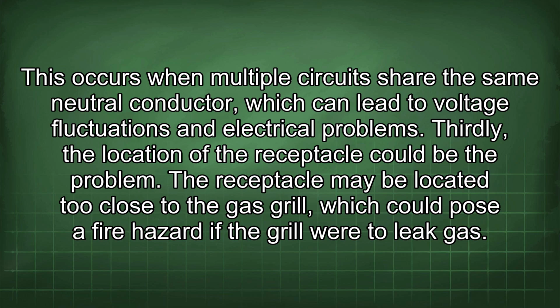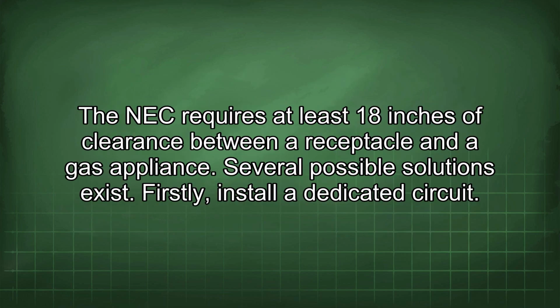Thirdly, the location of the receptacle could be the problem. The receptacle may be located too close to the gas grill, which could pose a fire hazard if the grill were to leak gas. The NEC requires at least 18 inches of clearance between a receptacle and a gas appliance.